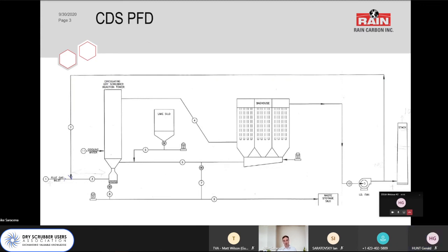Yeah, I think the acid dew point is a huge one. I would definitely recommend loss-in-weight feeders to measure fresh lime consumption at any new installation. It's almost impossible to optimize these systems without knowing how much lime you're using on a regular basis. If you don't have that, the best you're going to get is lime shipments, which are not a great metric. So certainly acid dew point monitors and loss-in-weight feeders. I would love to have a permanent installation of SO2 and CO2 analyzers at the inlet to the reaction tower. That would allow me to do mass balances at any interval I was interested in around the whole system. If I had those three things, I would be a pretty happy person, for sure.